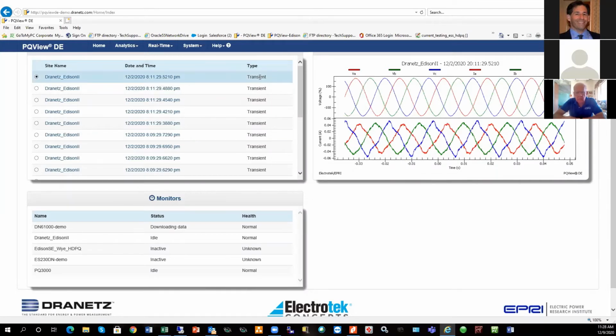A transient is a very common type of event that occurs within a subcycle. The instrumentation, depending on settings, can record transient faults that can be minute. At first glance you might say it doesn't look like it, it looks pretty sinusoidal, but there are actually minute changes from waveform to waveform, and depending on how sensitive the instrument is programmed, it can capture those as events.